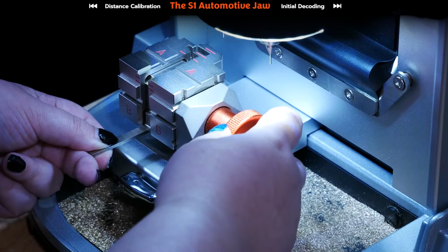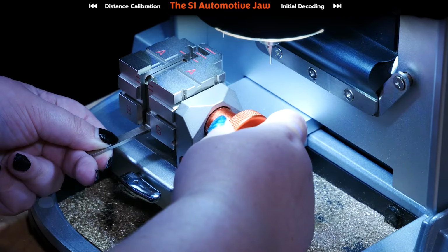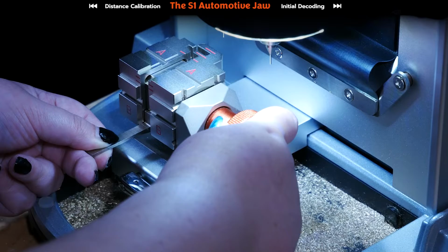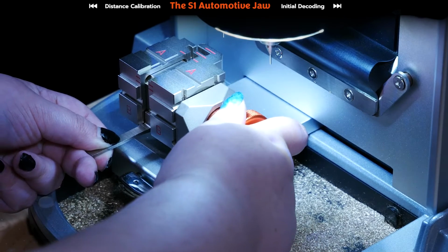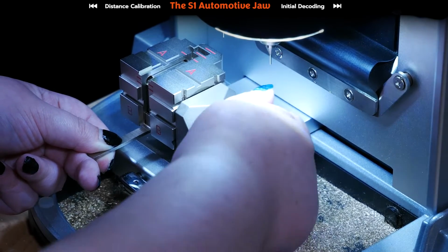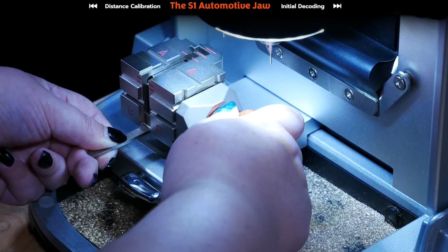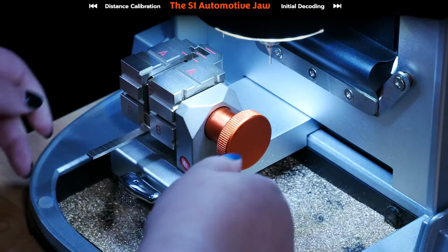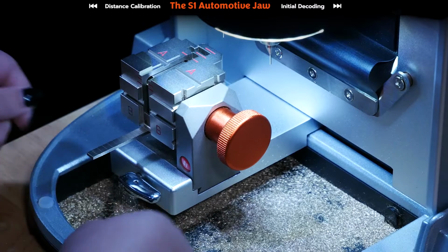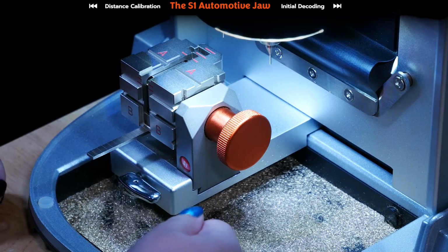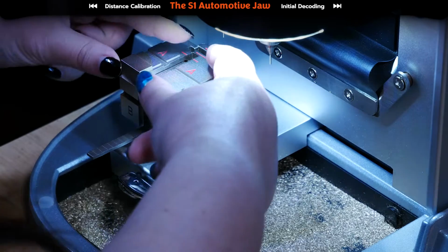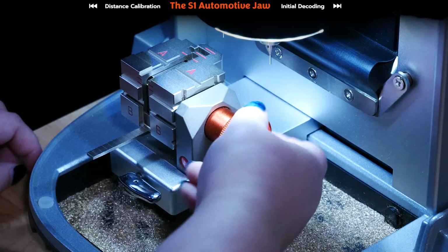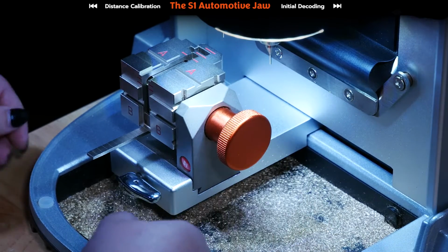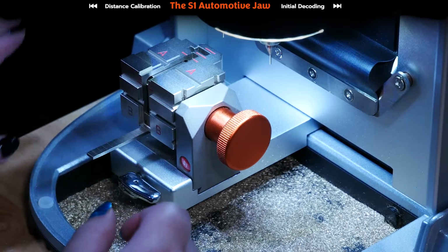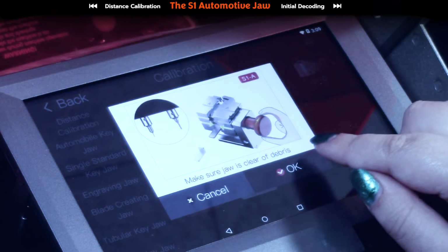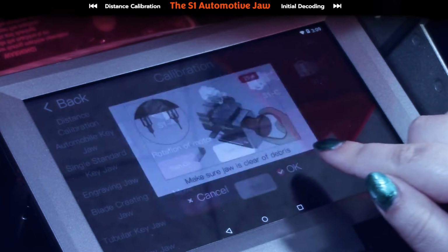So if you look closely, you can see I'm putting it in towards the bottom, kind of line it up with this B section at the bottom. And then you're going to just tighten it in place. Make sure you can't move it. You don't want to over tighten it because you can make the jaw go inwards, and you could possibly strip out this knob over here. But as long as it's secure and you can't move it, it's good to go. Back up on the screen, we're going to hit OK and start the calibration.